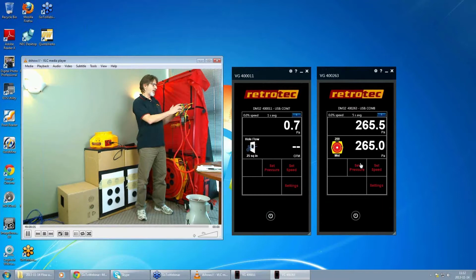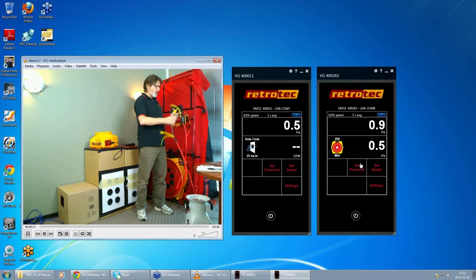So here I'm checking positive to positive. I'm going to disconnect that. I'm going to go positive, negative. And you'll see that that seems to be okay. Now I'm going to go negative to negative. So I've pretty thoroughly checked those two gauges on both ranges. And now I'm going to test the yellow tube to make sure the yellow tube is not blocked or leaks. And there we're checking the yellow tube and we notice it leaks. If we were to get a little razor blade and just put a tiny little cut in that tube, you notice that that pressure would drop off very, very rapidly.